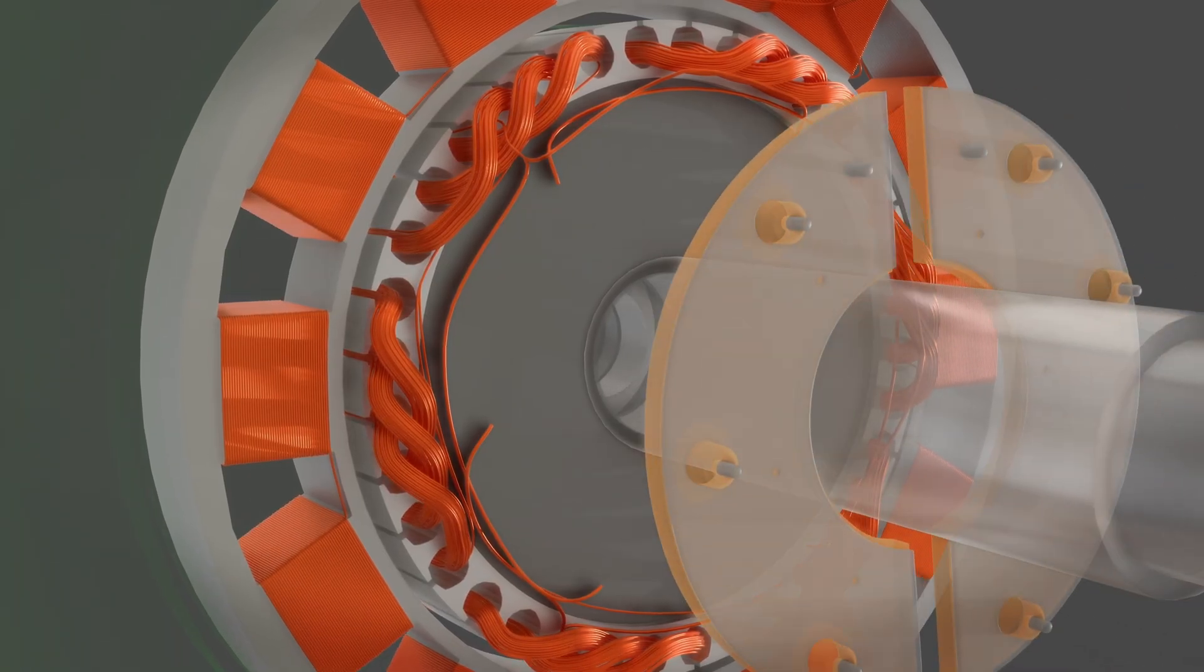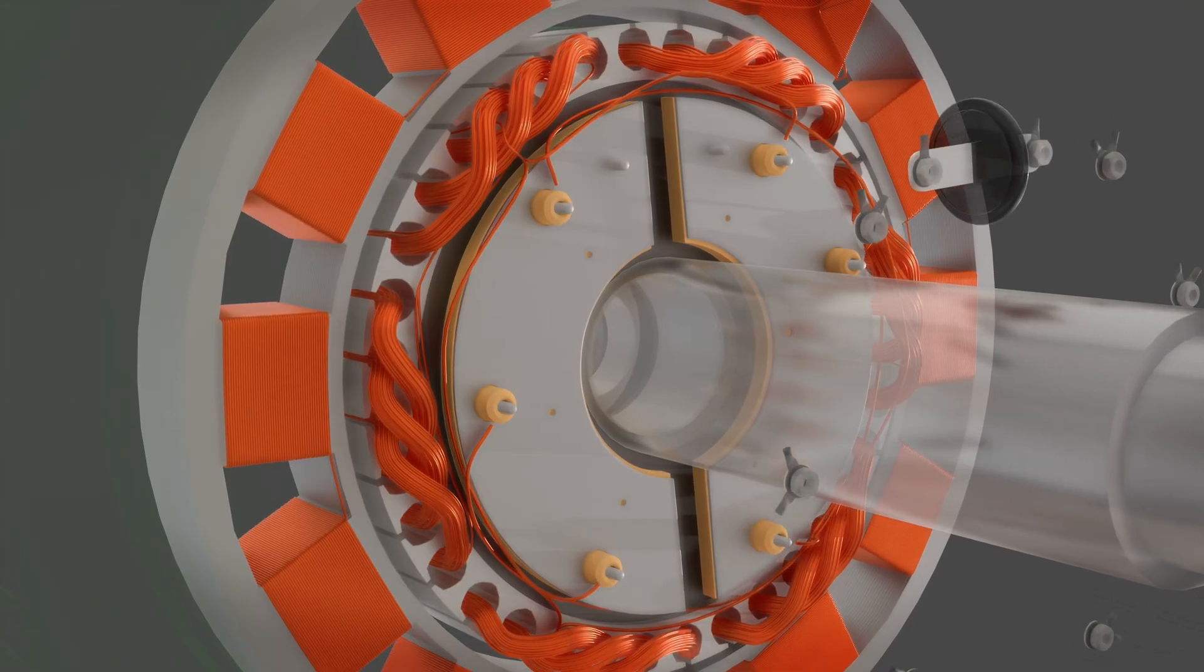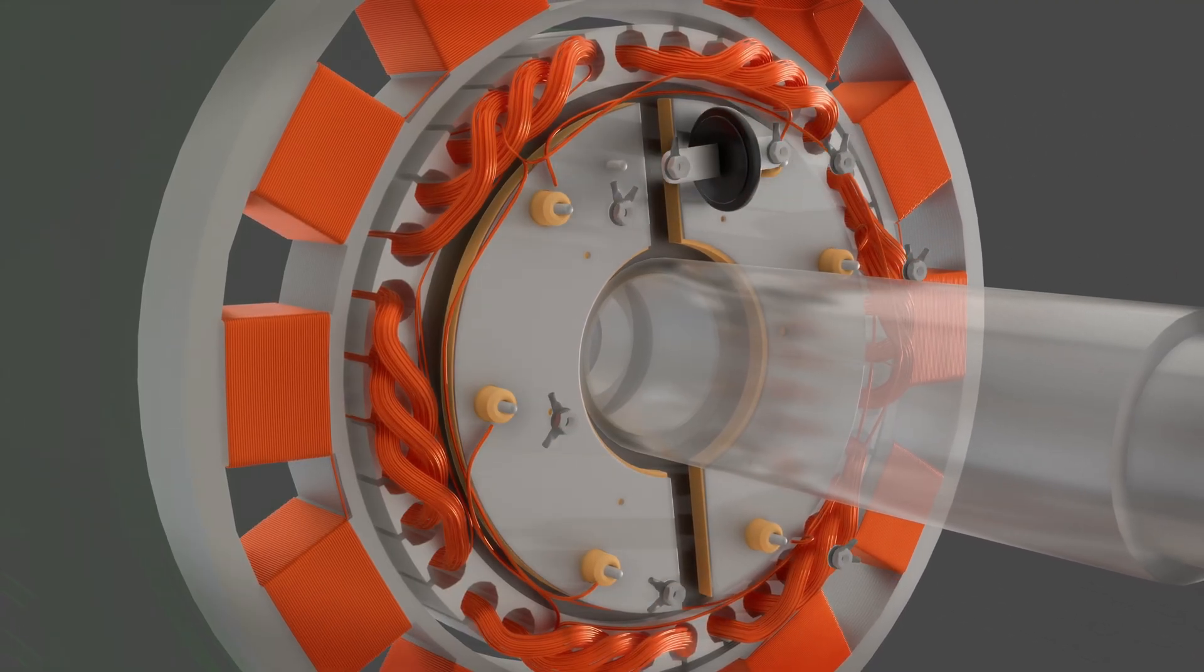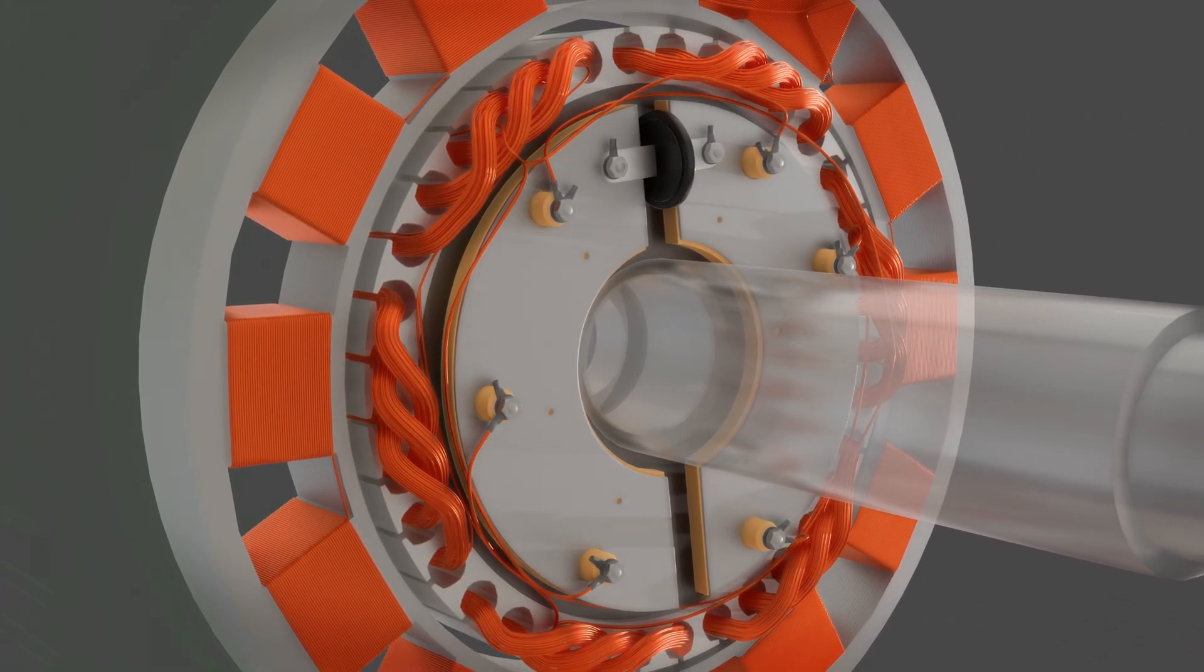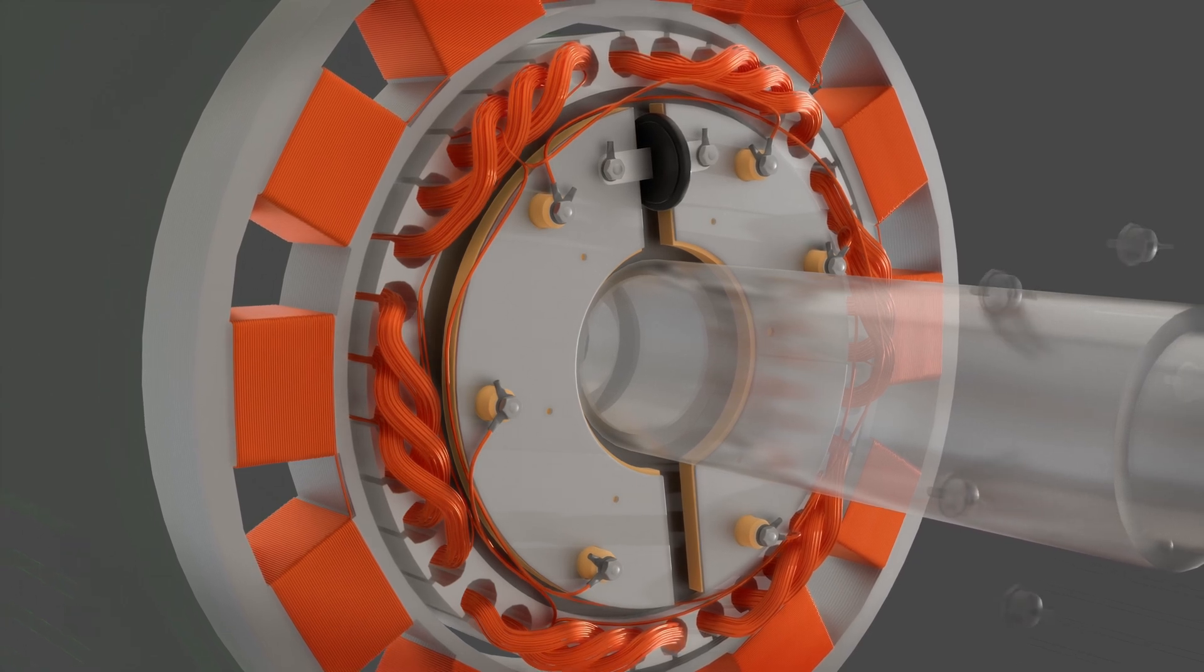Therefore, rotating rectifier diodes are used to convert AC to DC current. These rectifier diodes are mounted directly on the exciter rotor and rotate with it. Full-wave bridge rectification is used to convert AC to DC current.